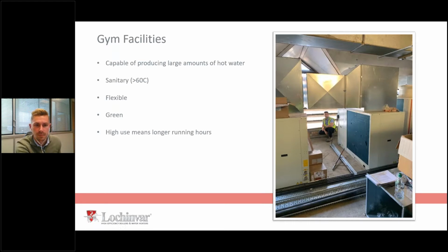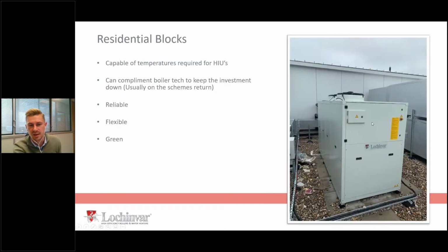In resi blocks, like I say, you can run at like 70, 80 degrees now. So if you've got demanding heat interface units that have these increased requirements for high temperatures, it fits in really nicely and effectively, and still gives you efficiencies in excess of 200%, which compared to comparable gas plant is a massive reduction in your CO2 emissions.